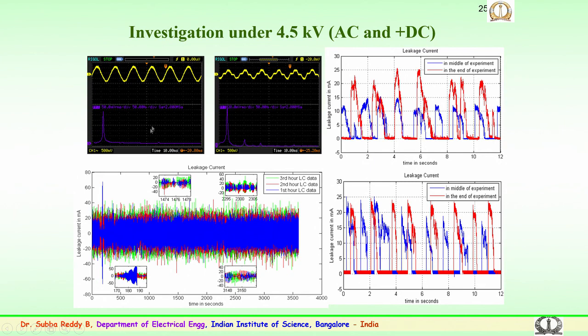During the process, the leakage current for various samples, in one of the experiments, is conducted at 4.5 kilovolts both for AC and DC application. You can see the discharges during the process, and these discharges, which are continuous in nature, have been recorded using a National Instruments module where long duration data could be captured and used for analyzing. So, we have seen various types of leakage current data here for 1, 2 or 3 hours, which shows the increase in magnitude for different time spans. This shows the leakage current in milliamps and time in seconds during the middle of the experiment. So, this is how the performance is monitored.